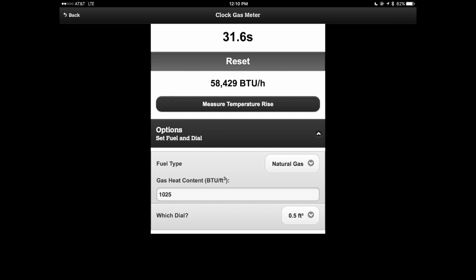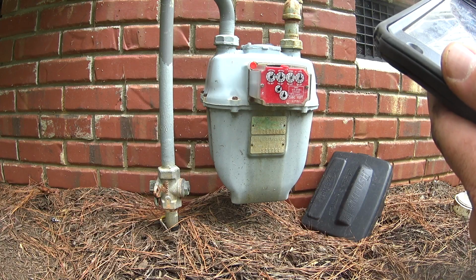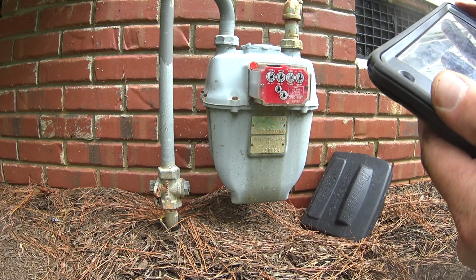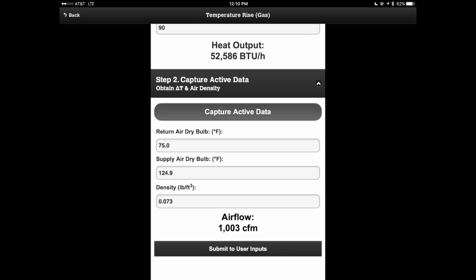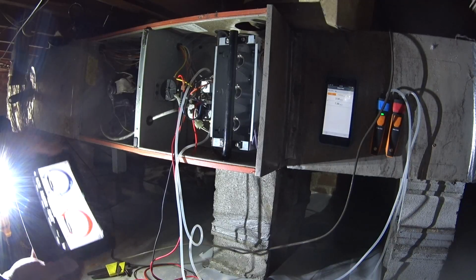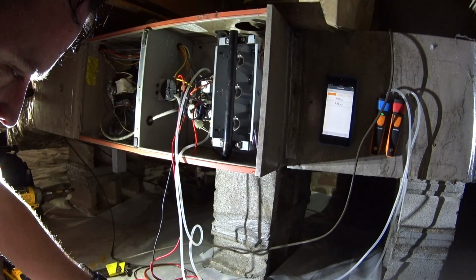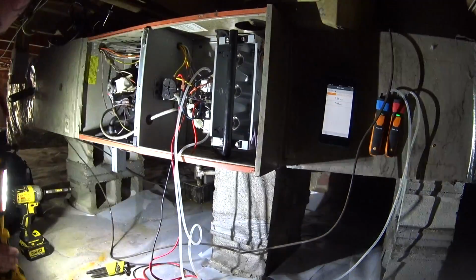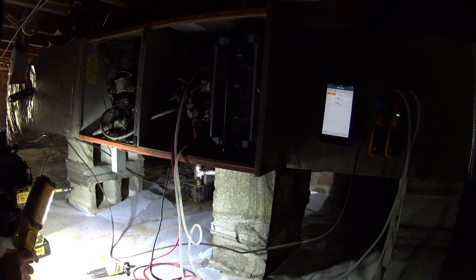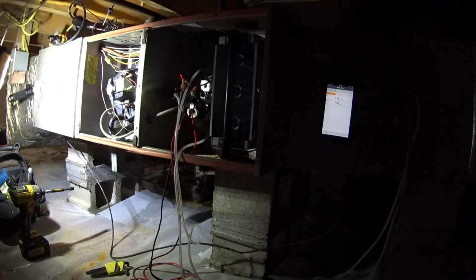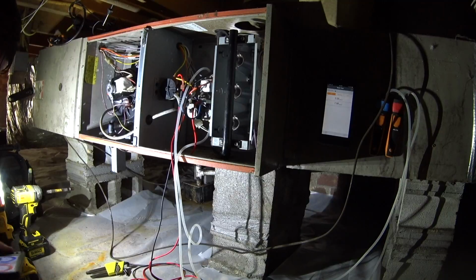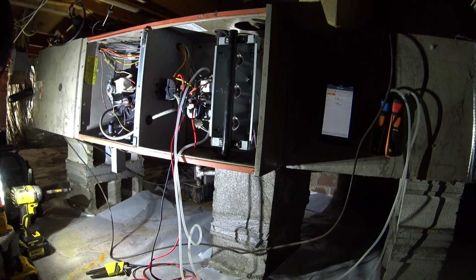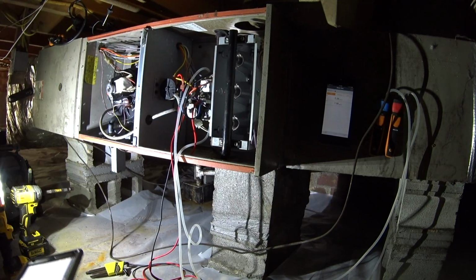Pretty happy with that. We are 90% efficient. Capture active data, and we show 1,000 CFM at the current temperature rise. Back inside, we're going to capture those measurements and shut it down before we cause too much heat inside. Return air is showing 75 degrees and 126 supply, but wanted to make sure we got our combustion numbers also before we shut it down.